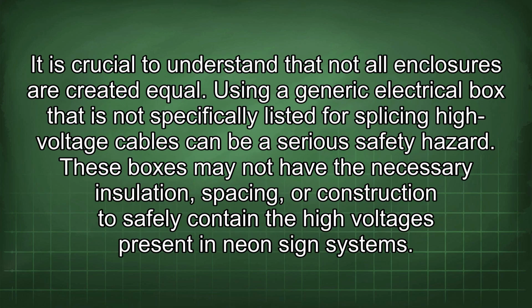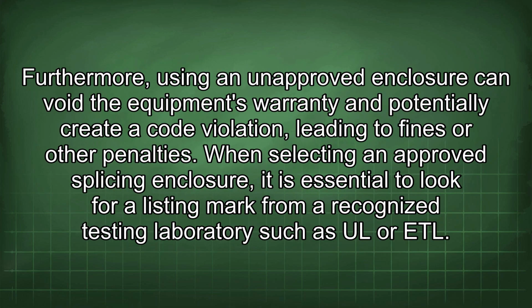It is crucial to understand that not all enclosures are created equal. Using a generic electrical box that is not specifically listed for splicing high-voltage cables can be a serious safety hazard. These boxes may not have the necessary insulation, spacing, or construction to safely contain the high voltages present in neon sign systems. Furthermore, using an unapproved enclosure can void the equipment's warranty and potentially create a code violation, leading to fines or other penalties. When selecting an approved splicing enclosure, it is essential to look for a listing mark from a recognized testing laboratory such as UL or ETL.